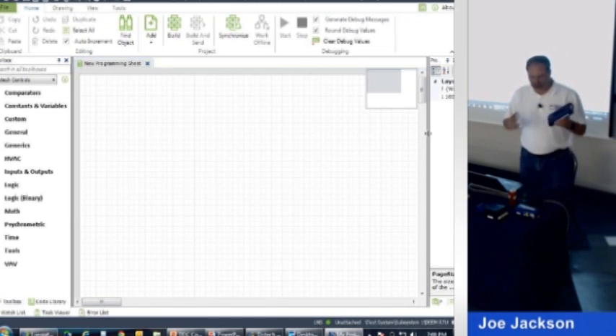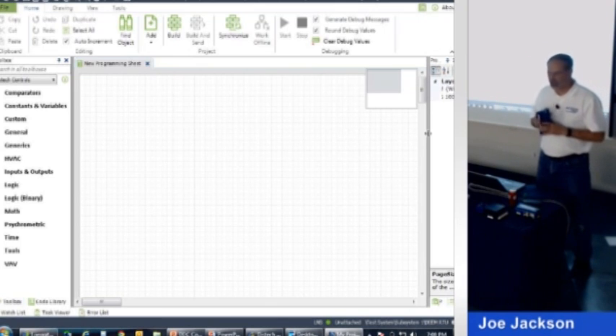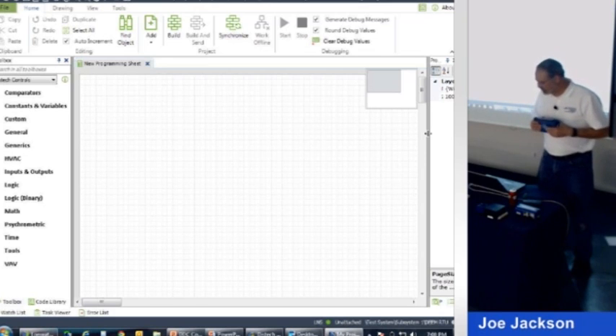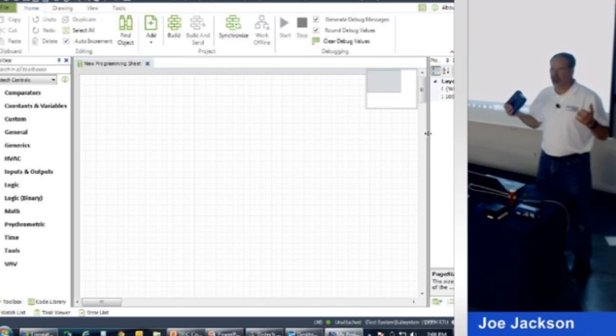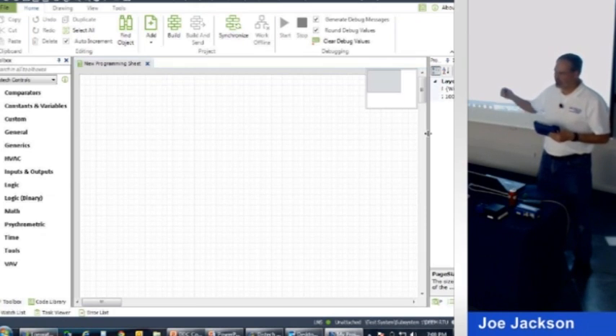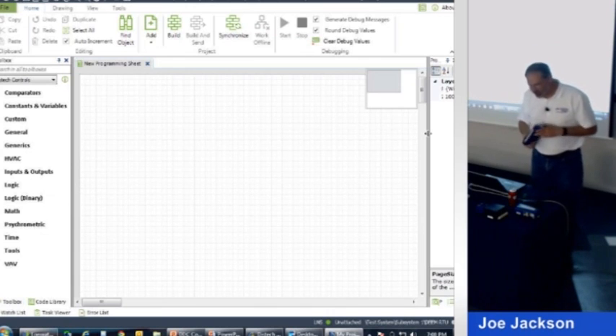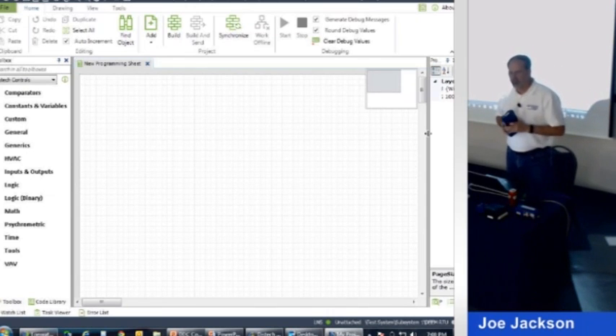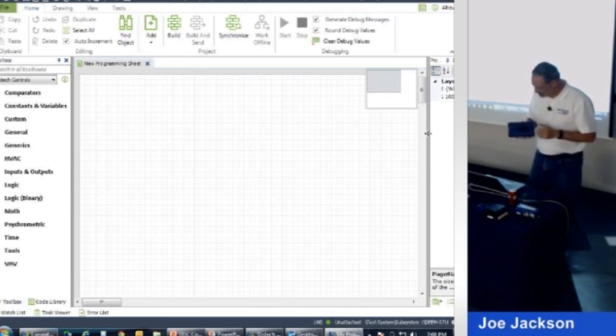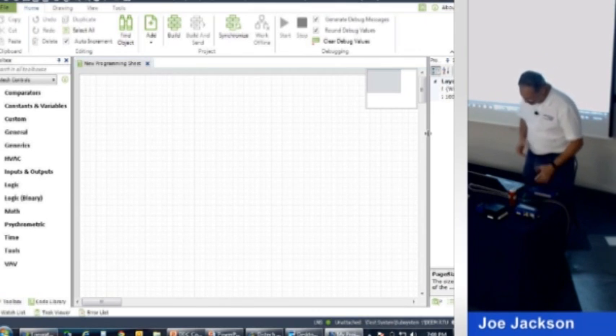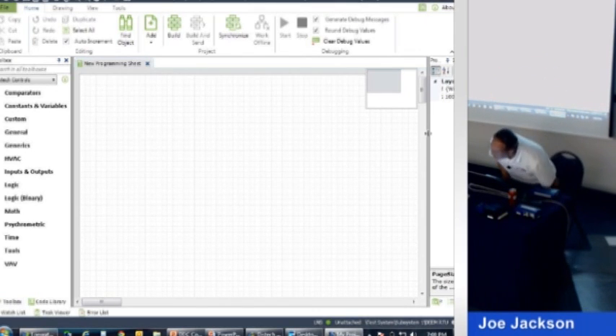You know, you've got 5 sensors on the system and it's not running yet, and you look at it on your screen and they're all 78 degrees. Well, how do you know the electrician ran to the right spot? Well, you get your buddy and say, go to the chilled water supply temperature, and he unwires it and you watch it fail. And so you can wrap up 3 days in a simple chilled water plant if you wanted to. But we're going to do just a couple of quick things just so you get a feel for how the programming works.